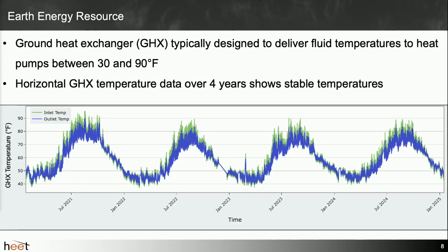And the reason why these systems are more efficient is because of this sine graph here. So the source temperatures going to that heat pump from the ground heat exchanger range between around 40 to 90 degrees Fahrenheit, sometimes as low as 30. But this specific graph is collected from 4 years' worth of data in a very cold climate in Winnipeg, Manitoba. So during this same time period, the outdoor air temperature ranged from -20 to plus 100 degrees Fahrenheit.